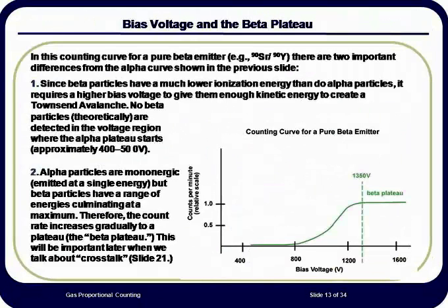However, if we increase the voltage, we can locate a similar plateau for beta particles as for alpha particles. The major differences are the more gradual knee until the plateau, and the rate of change on the plateau is slightly greater than for alpha particles at their plateau.